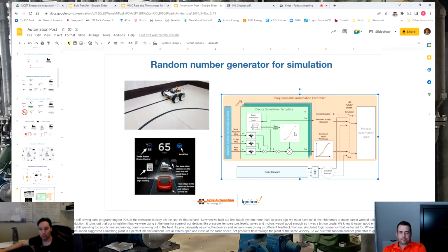We do test with it. One of the things we do is throw one bit that switches it over from real devices into fake, simulated devices. All of your valves giving discrete inputs and outputs, those are easy. Same with your VFDs. We do flow rates and temperatures, and then tank levels. It gets to the point where operators are convinced that it's real.